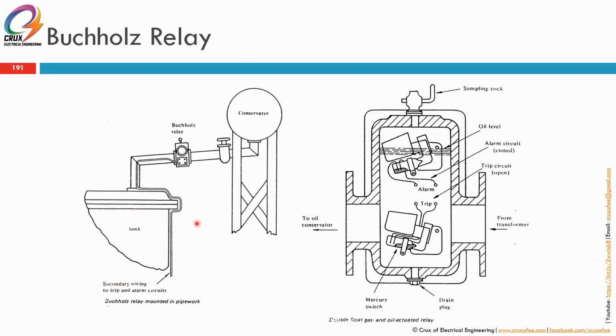So this is the Buchholz relay. It's normally located between your conservator and the tank. So the piping is a little bit slanted for gravity flow. So if there's any gas coming in, the gas will fill up this part. Under normal condition, the oil is filled all the way up here. So don't forget to bleed your Buchholz relay during first commissioning or after oil filtration. You must make sure that the oil is filled up all the way to the top.